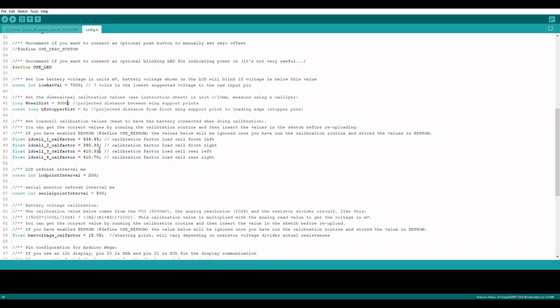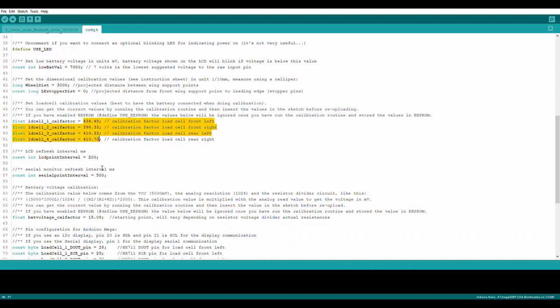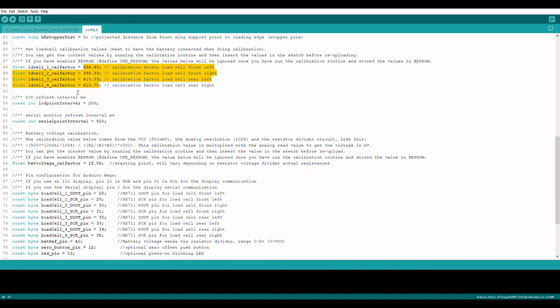These are my current load cell factors that I just hand typed in, but that's where they'll start. They should get you close to the right calibration if you don't have a known weight, somewhere in the neighborhood of 400 basically, but you can see the difference, how each one can be different. This is the load cell print interval, basically every 0.2 seconds, and this is the serial print interval, every half a second. Those can be changed.